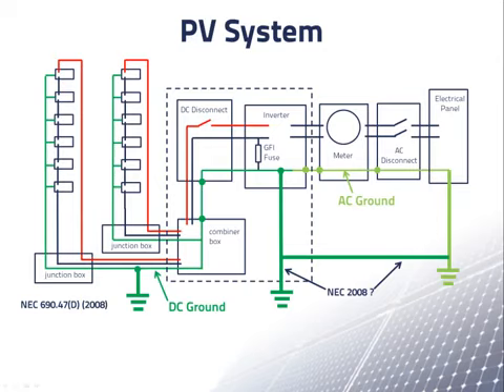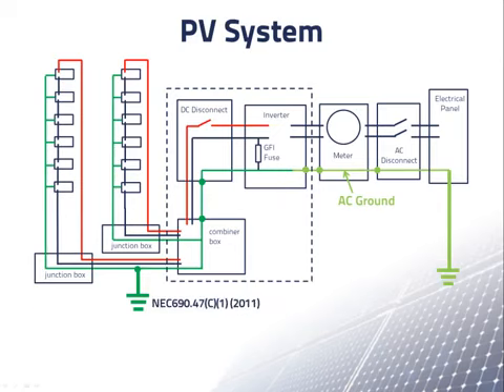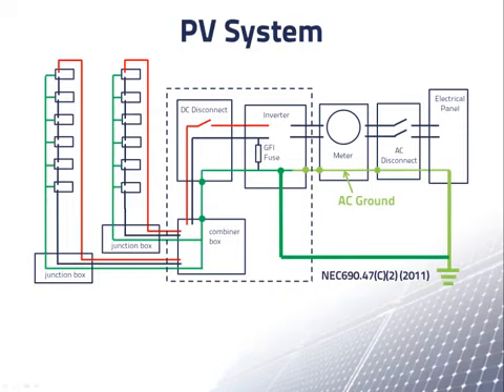Finally, the 2011 NEC gave several alternatives for grounding. One option is a connection to a grounding rod at the array. This is a good choice if the array is on the ground and separated a little from the building. The direct connection to a grounding rod can also be from the point in the inverter where the DC and AC grounds meet. This is the requirement from the 2008 NEC and earlier versions. The NEC also allows this connection to be an existing ground also used by the electrical panel.